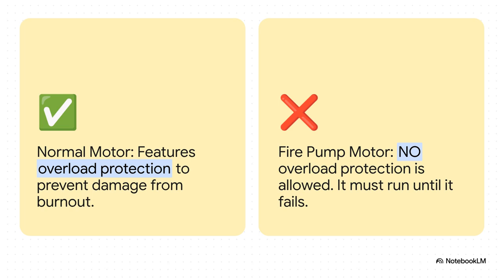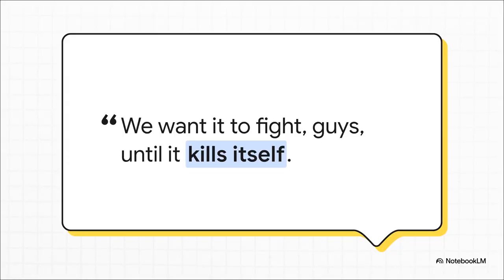But for a fire pump? Nope. The code flat out forbids it. No overload protection allowed, period. And this quote from an electrical instructor just says it all. It really gets to the brutal core logic of the whole system. The system doesn't care if a bearing is seizing up or if there's a clog in the pipe making the pump work harder. It doesn't want to save the motor. It wants that motor to keep fighting, even if it means destroying itself in the process.